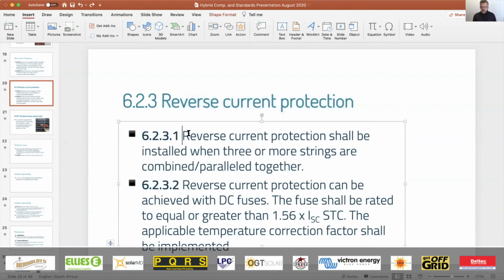Reverse current protection shall be installed when 3 or more strings are combined or paralleled together. Reverse current protection refers to fuses on both the positive and negative side of the cables or strings, and it can be achieved with fuses. The fuse shall be rated to be equal or greater than 1.56 times the short circuit current.